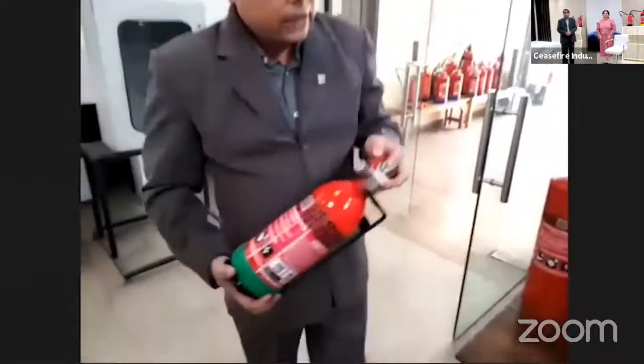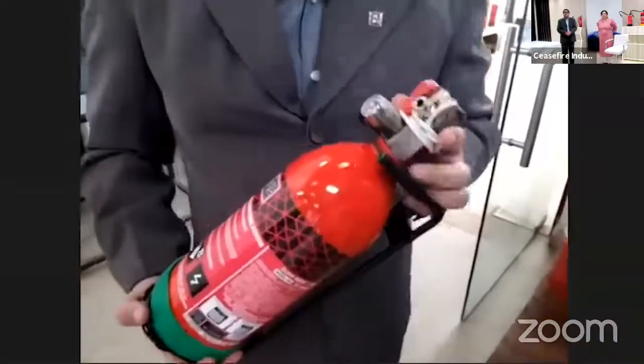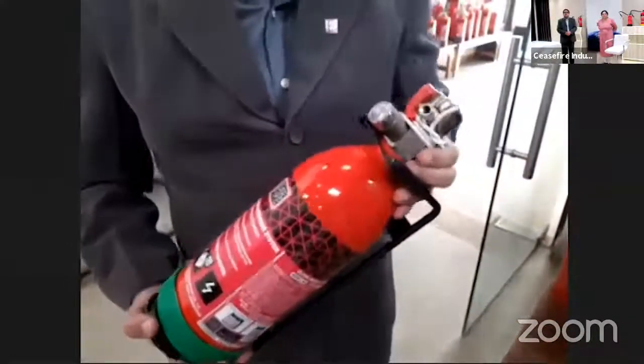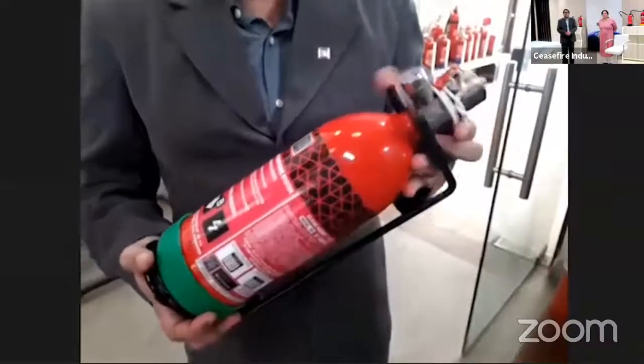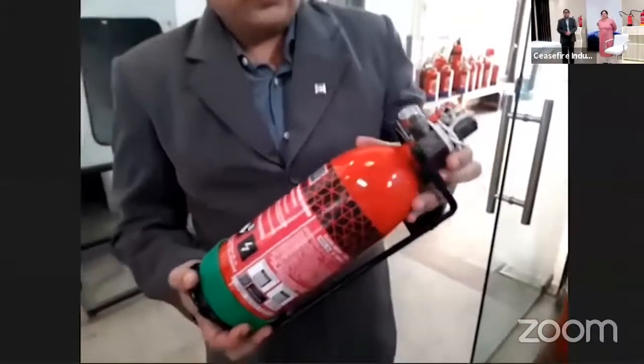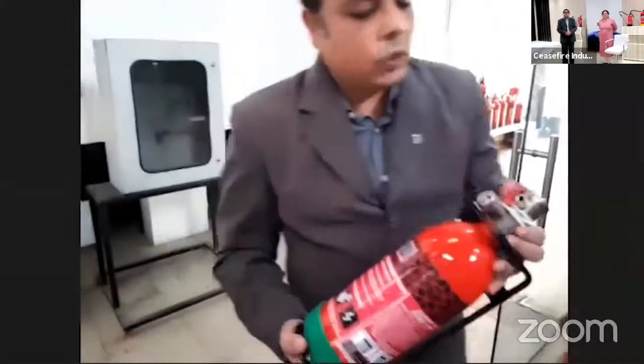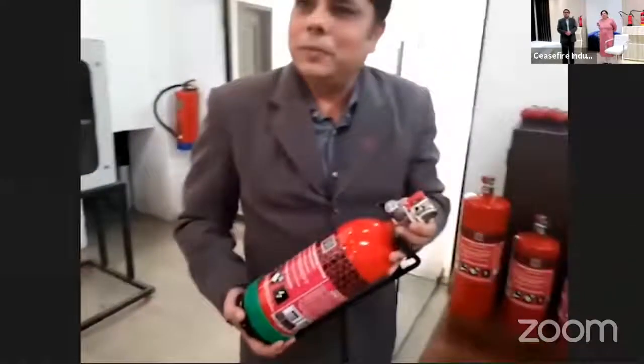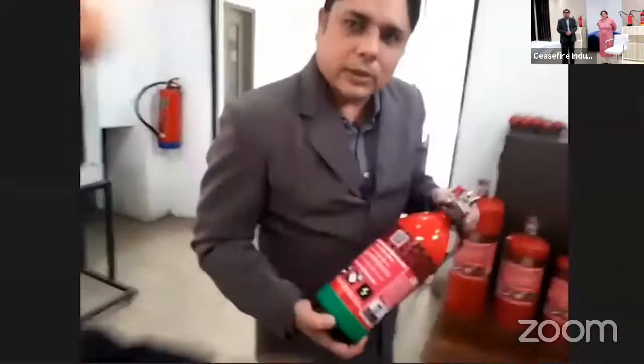The heat sensing tube will burst open as soon as it detects a fire, and the extinguishing agent pressurized within the cylinder would come out from the same miniature hole. This would be the direct system, so therefore it is called direct. What is the other version we have?